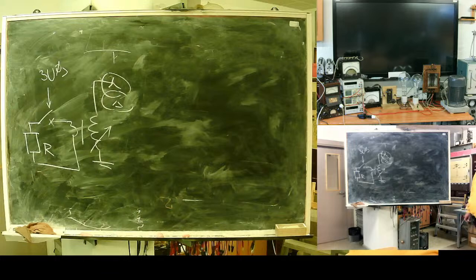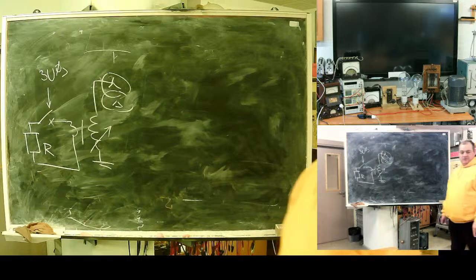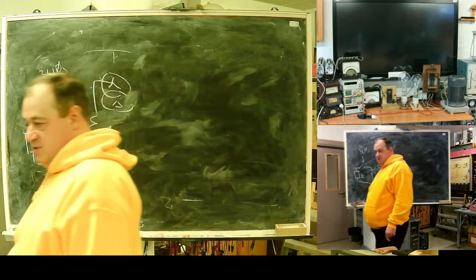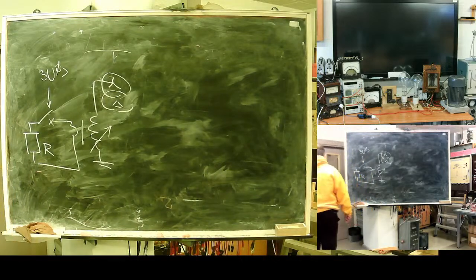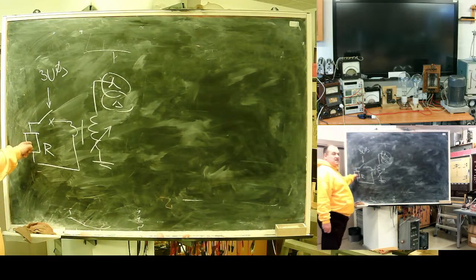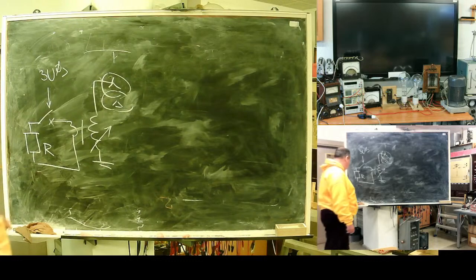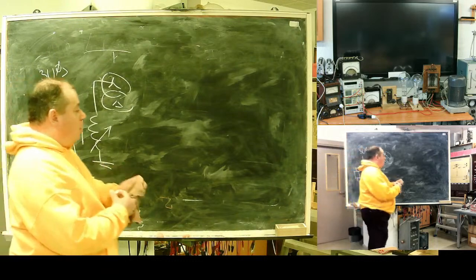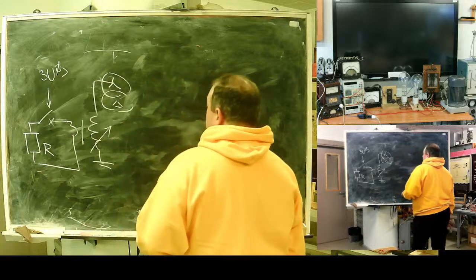Remember, 100% non-operation of earth fault protection caused damage or death. The protection engineer will be the one to blame. Will become, say, the scapegoat. Make sure this resistance is in a check plan. And operation of this switch is in the check plan. Okay, so where are we?